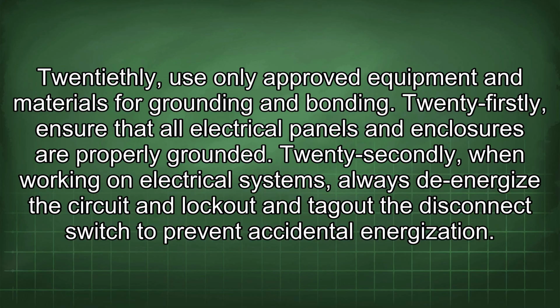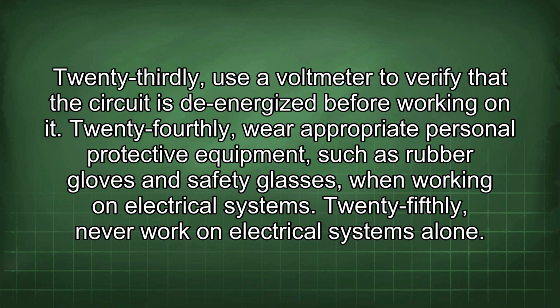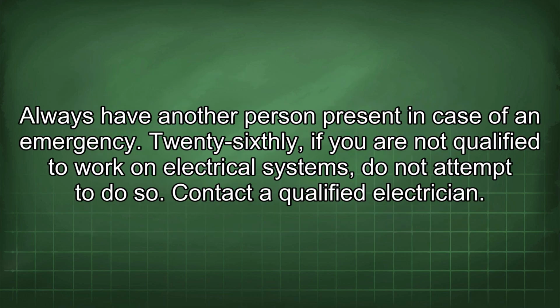22ndly, when working on electrical systems, always de-energize the circuit and lock out and tag out the disconnect switch to prevent accidental energization. 23rdly, use a voltmeter to verify that the circuit is de-energized before working on it. 24thly, wear appropriate personal protective equipment, such as rubber gloves and safety glasses, when working on electrical systems. 25thly, never work on electrical systems alone. Always have another person present in case of an emergency.